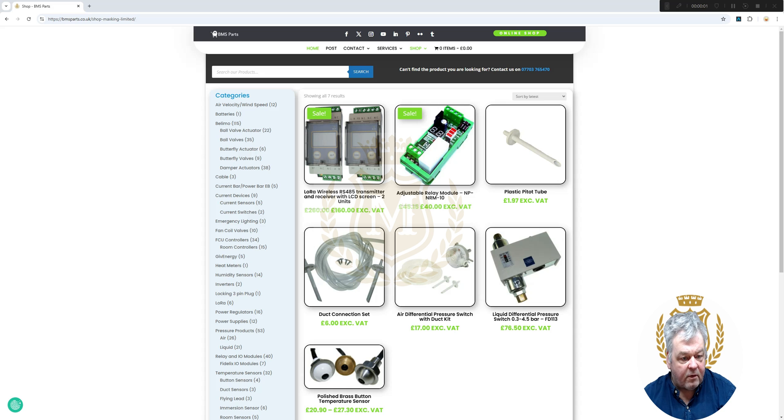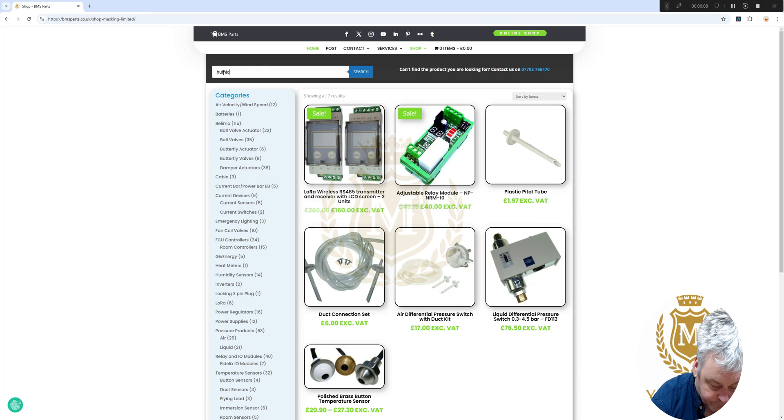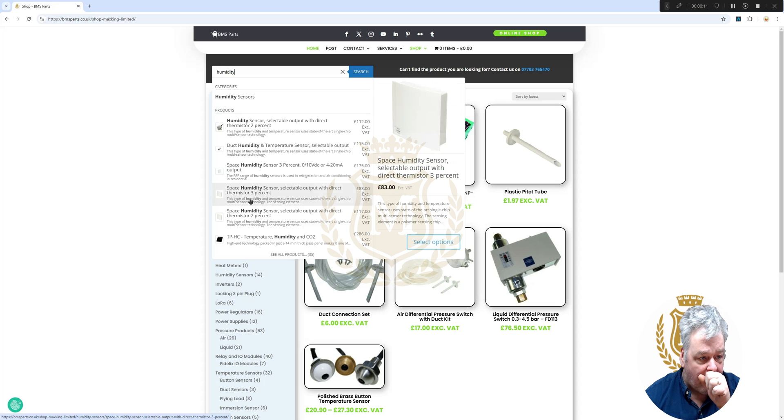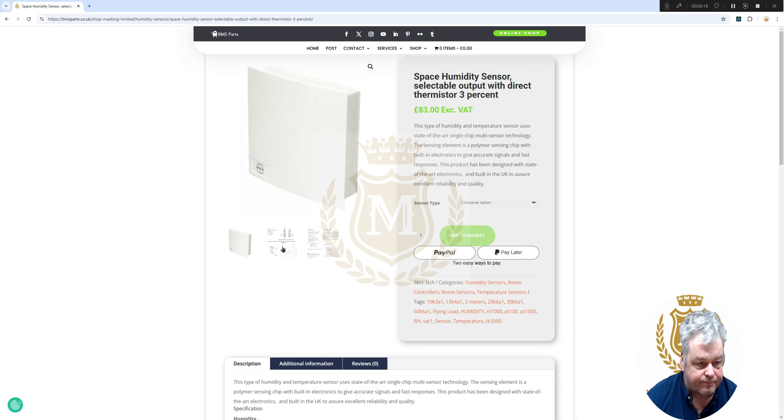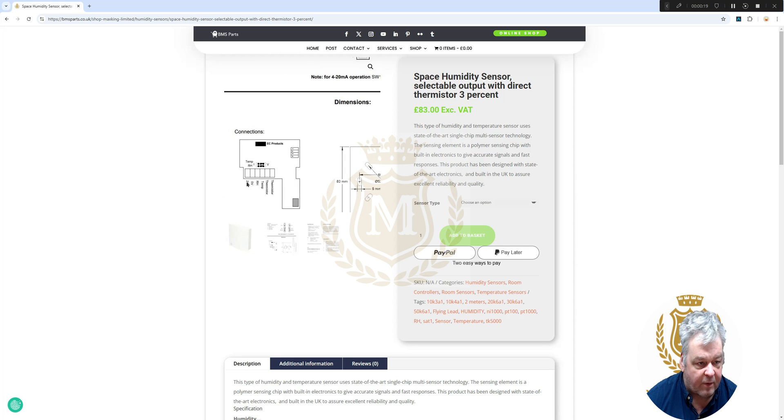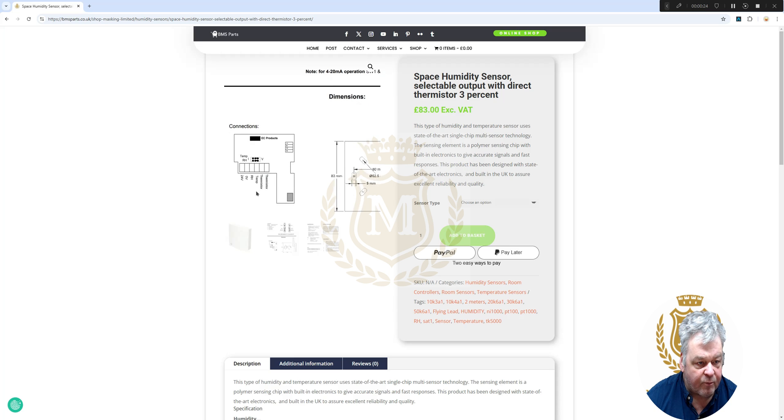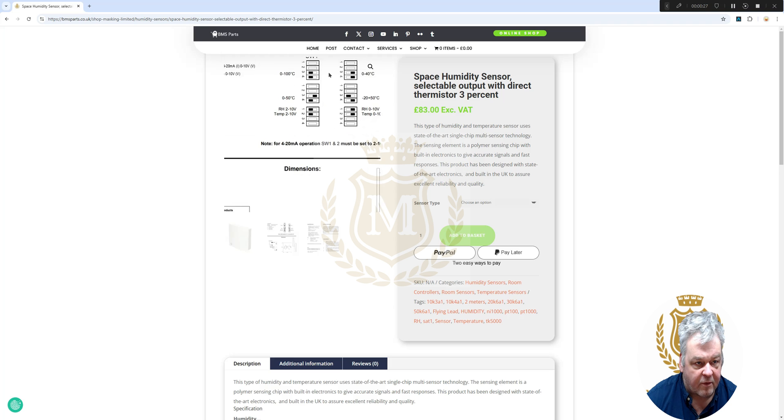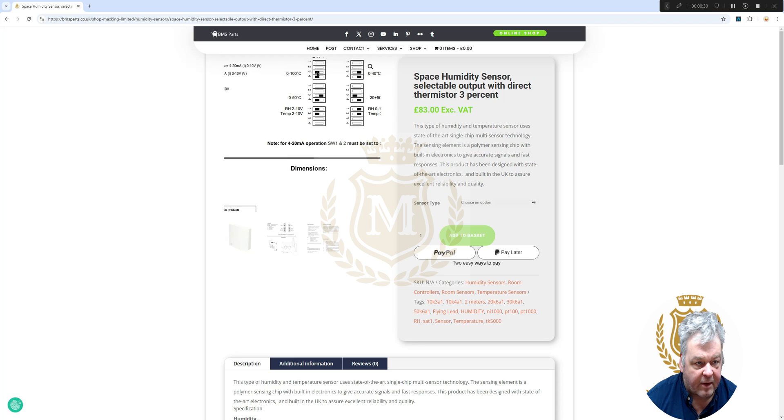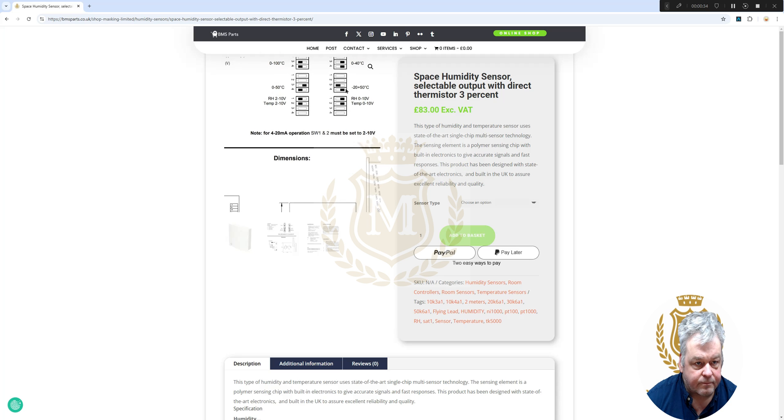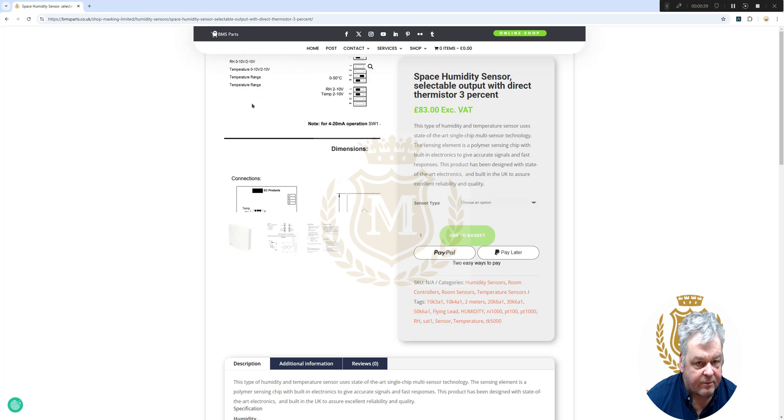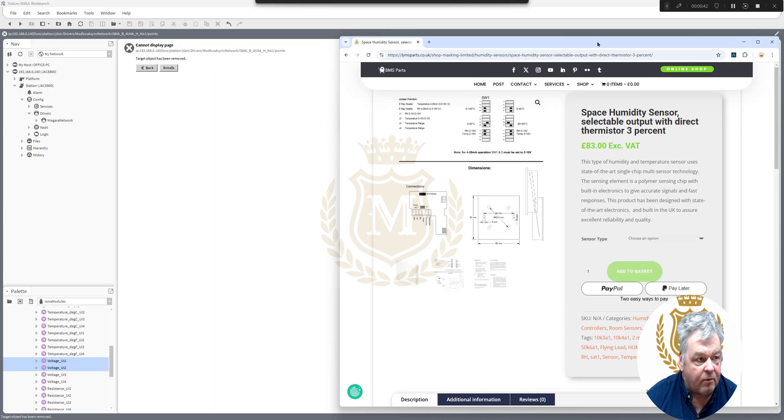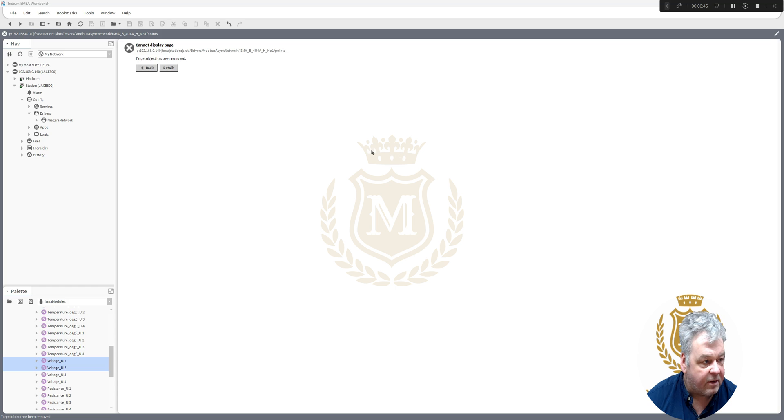So we've got a humidity and temperature sensor. Let's just find that for you in BMS parts. It's a wall mounted unit. We've got our 24 volts AC in there and then we've got humidity, temp, and we can put a thermistor if we want to. We've got the dipswitch settings up here, 3 and 4, so 0 to 100 and 0 to 10. It's set up there as well. So now we'll go back and move that across to the other screen.